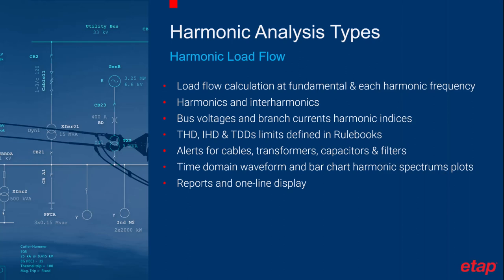ETAP provides multiple analysis types. The harmonic load flow study carries out load flow calculations at the fundamental frequency. Then the fundamental voltage and current results are used to calculate different harmonic indices. The simulation considers each harmonic frequency at which any harmonic sources exist in the system, including both harmonics and interharmonics. The computed bus voltage THD, IHD, and the branch TDD and IHD are compared with their limits as specified by the selected harmonic rulebooks.